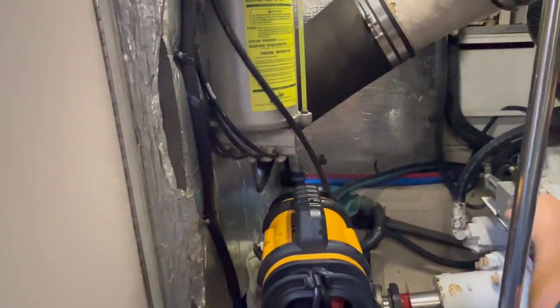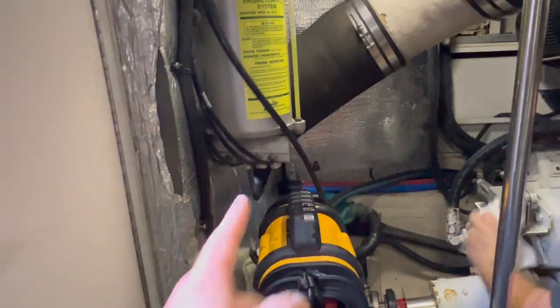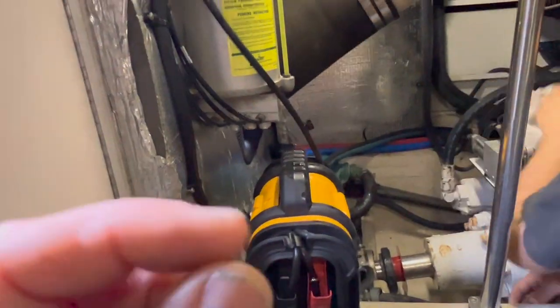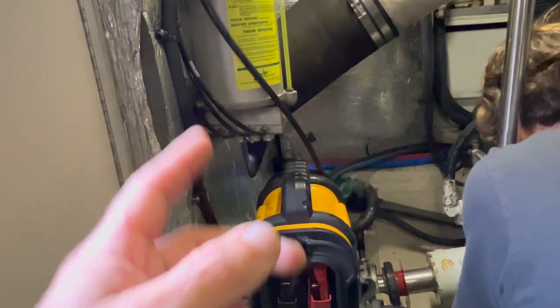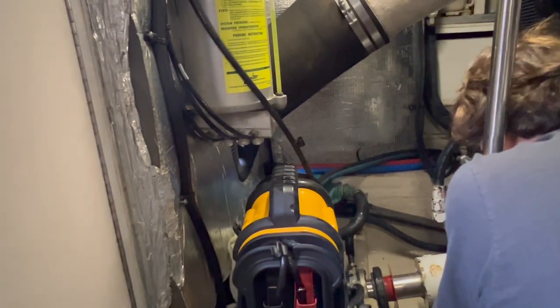We went to the bridge and ripped apart the shifter and we weren't getting anything on the supply side, so I kind of knew it was the charging valve. We came down here and the charging valve head was completely frozen - almost didn't get it out. Once we got that out we cleaned it all out; there are tiny little orifices in there that sometimes stuff will get stuck in. Once we did that, we pressurized it up to 20 pounds and we started getting fluid up to the bridge.